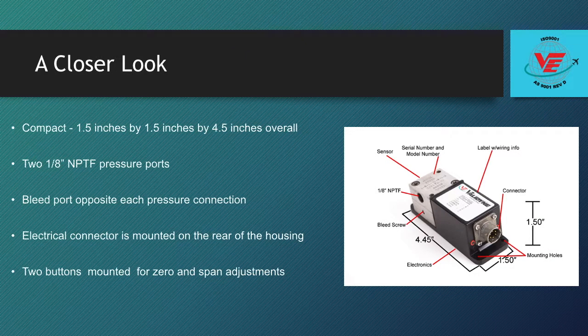The compact P855 has dimensions of roughly 1.5 inches by 1.5 inches by 4.5 inches overall. There are four 0.156-inch mounting holes on the corners of the base plate for easy installation to any flat surface. The standard pressure port is 1/8 inch national pipe thread. Swagelok adapter fittings can be used to connect the P855 directly to steel tubing.